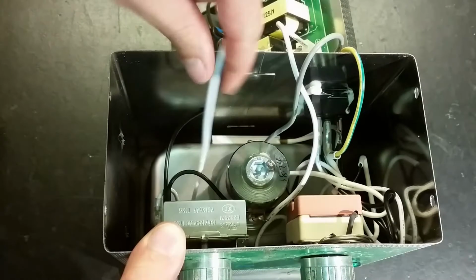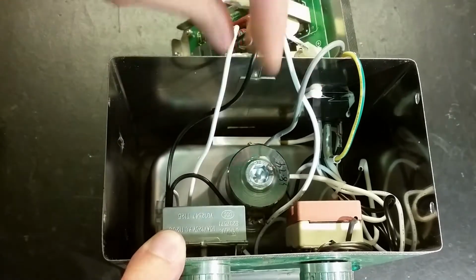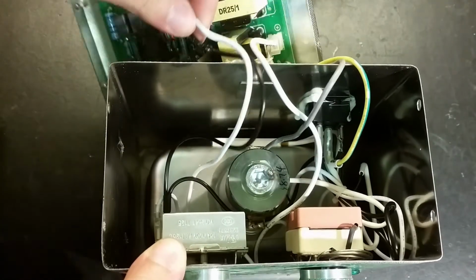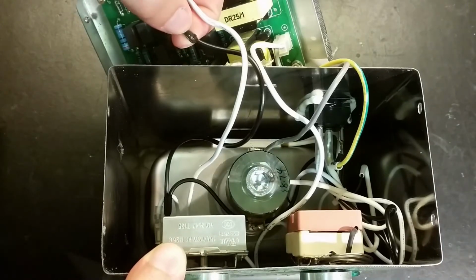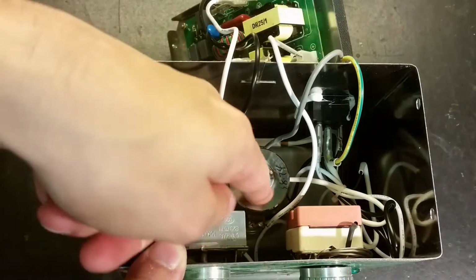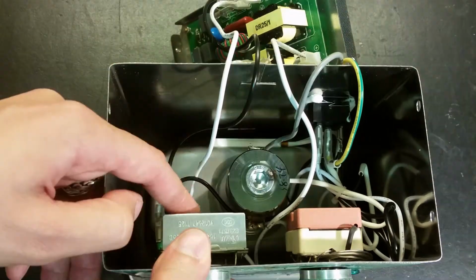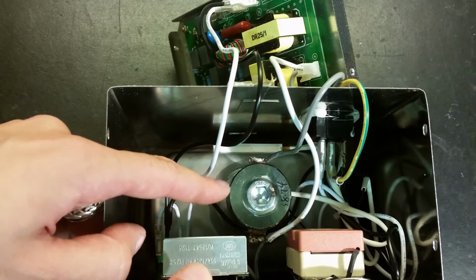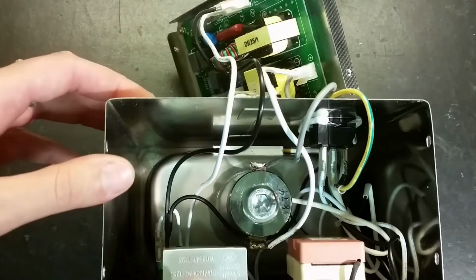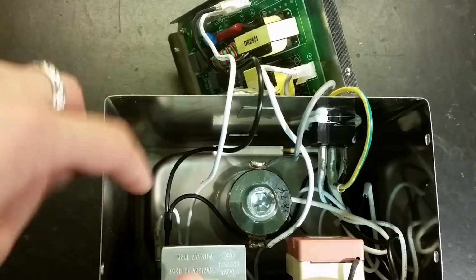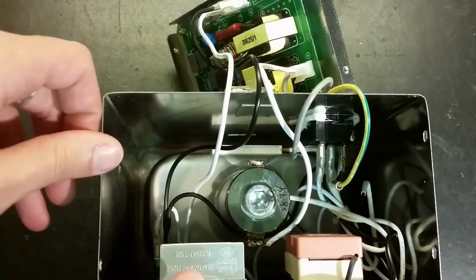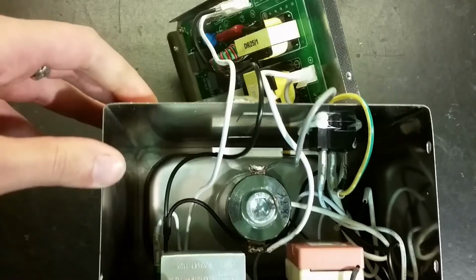This one is melted, this white one is melted in this spot, and the black one is completely melted through and shorted out to the transducer. The transducer actually gets hot enough to melt the wire — I didn't know that, because the tank itself shouldn't get more than about 90 degrees Celsius or so.